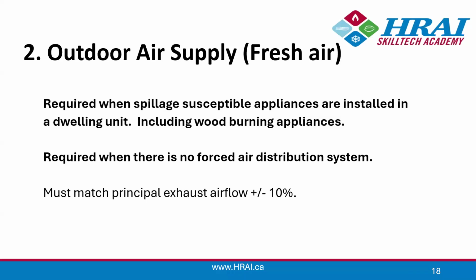But we're just going to follow through the code the way it's written so that you can understand what's being said here. So whenever you have a spillage susceptible appliance installed in a dwelling unit, including a wood burning appliance, then you must have the fresh air component. So we've got mechanical exhaust, we'll need to have mechanical fresh air.